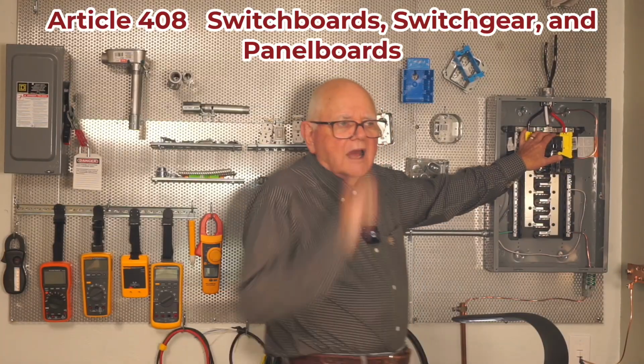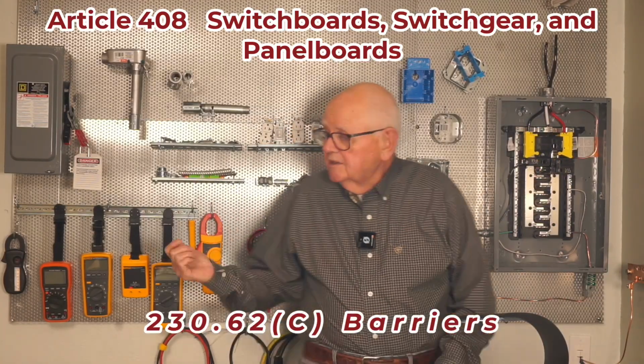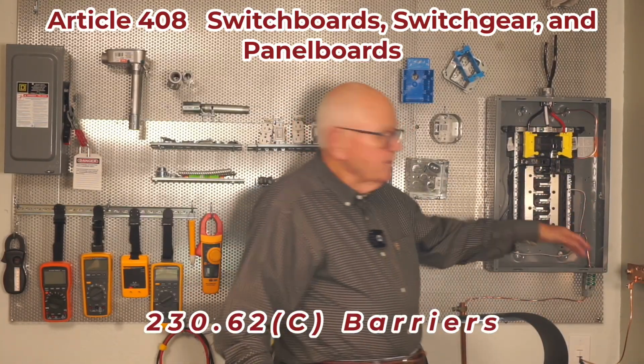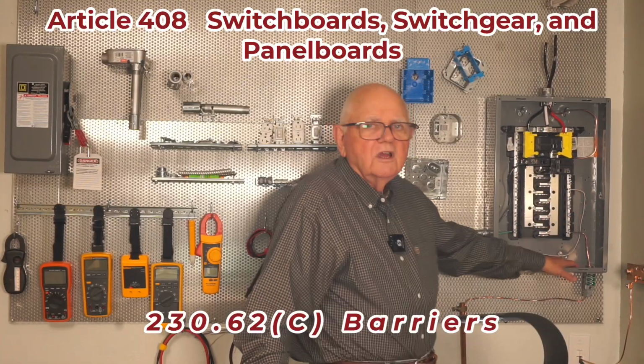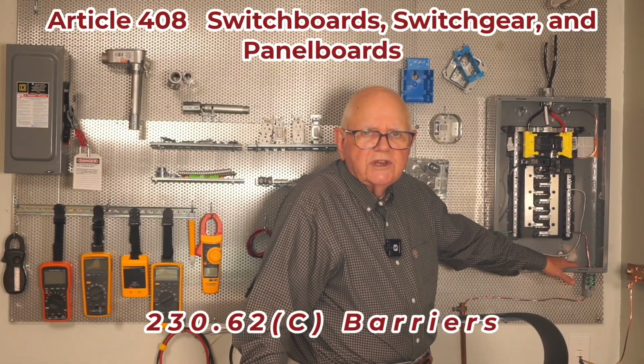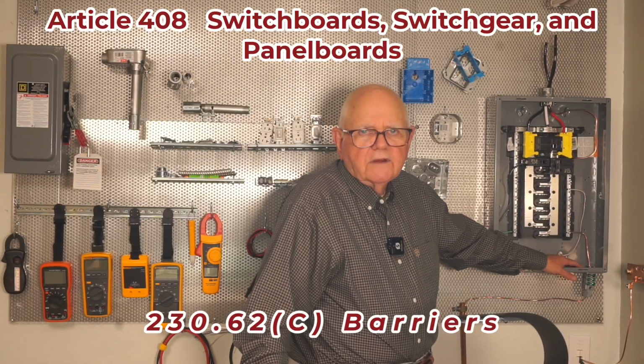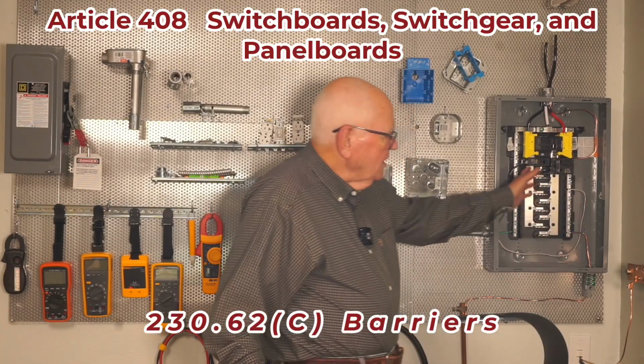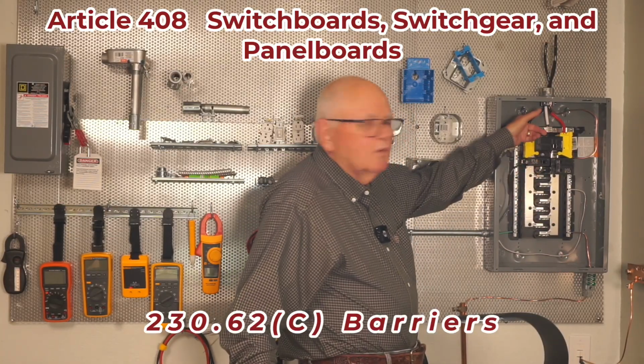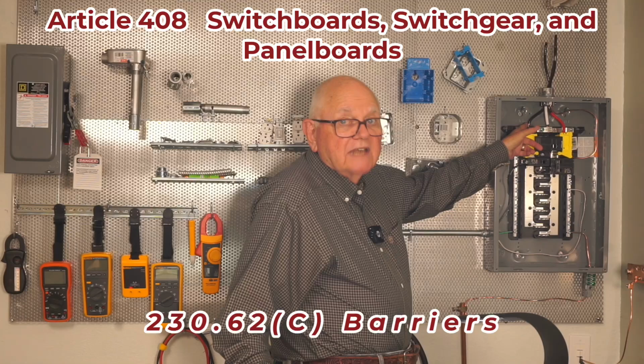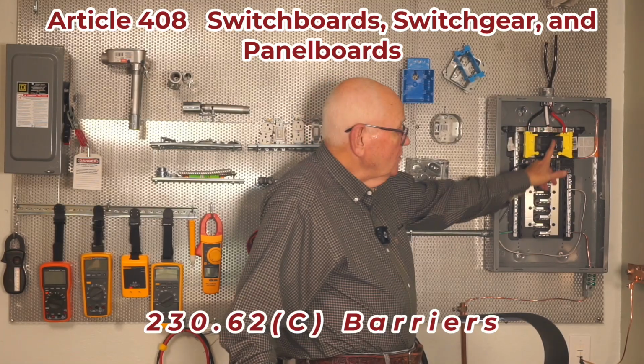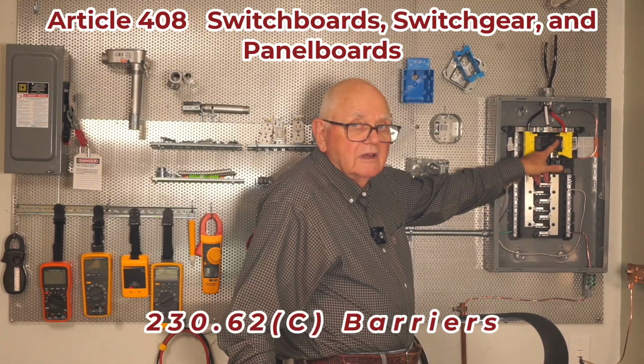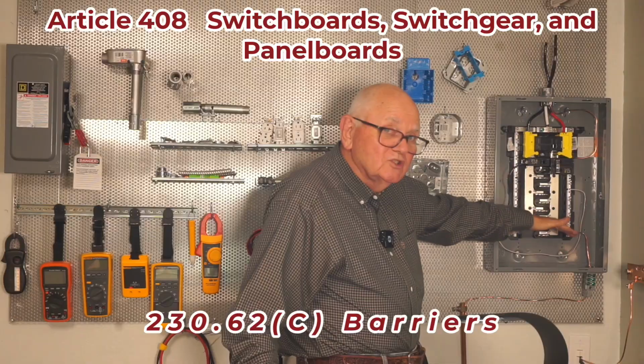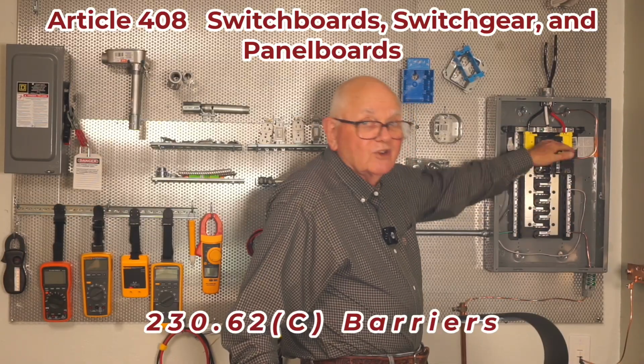Think about it. I'm going to come in here and grab one of these meters and maybe do some voltage testing for lockout, tag out, or whatever it is. Just do some troubleshooting, and I need to read some voltage in here. I don't want to be in here reading voltage and accidentally touch one of these terminals that attach to my ungrounded conductor.